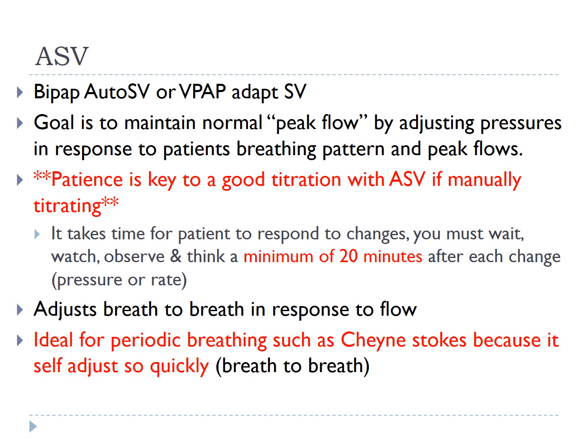ASV. This is adaptive servoventilation. The two brands that we've talked about are BiPAP Auto SV or VPAP Adapt SV. With this device, the goal is to maintain normal peak flow by adjusting pressures in response to the patient's breathing pattern and peak flow. One of the key things to titrating this device is patience. The patient's breathing will adjust, but it takes a lot of time, so you don't want to be titrating too quickly. With this device, we have to let the machine do its job, and so we need to not adjust the pressure any sooner than 20 minutes apart. You just have to let the machine work.